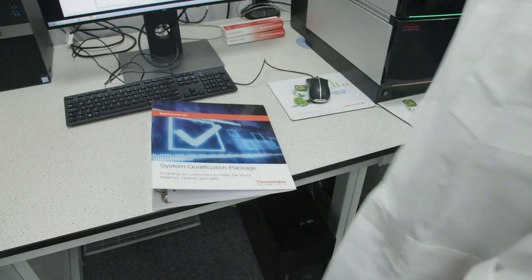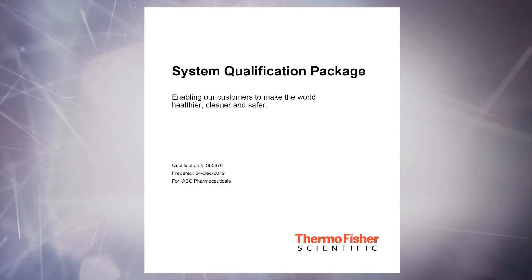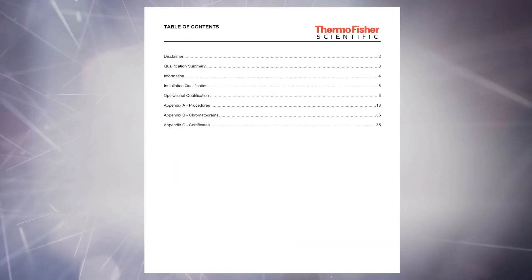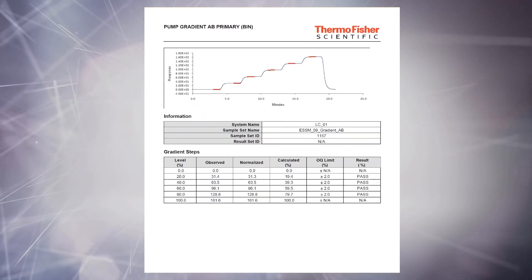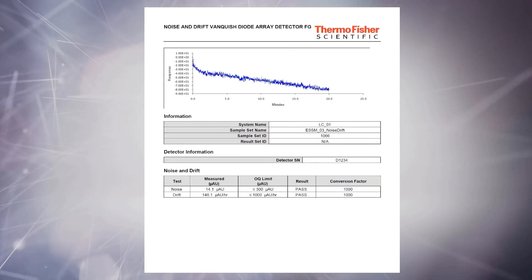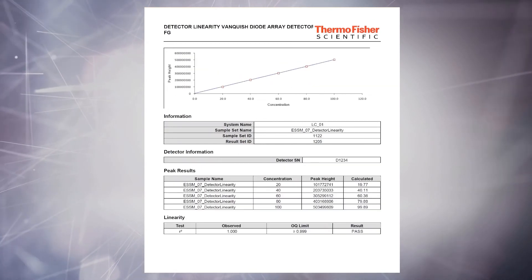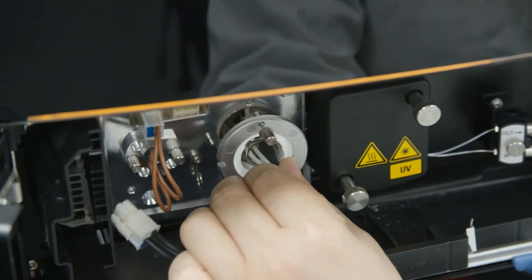Once all IQ and all OQ procedures have been completed, all external reports and documentation including chromatograms, test equipment and certificates and training documentation are collated and provided in an audit-ready electronic file or binder.